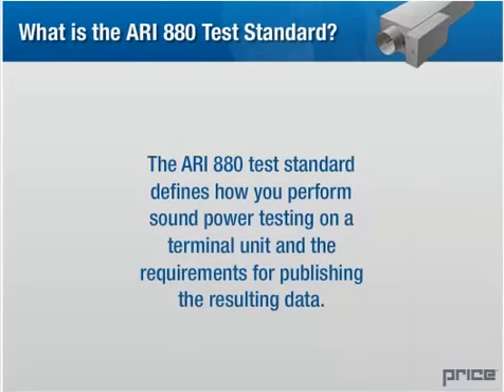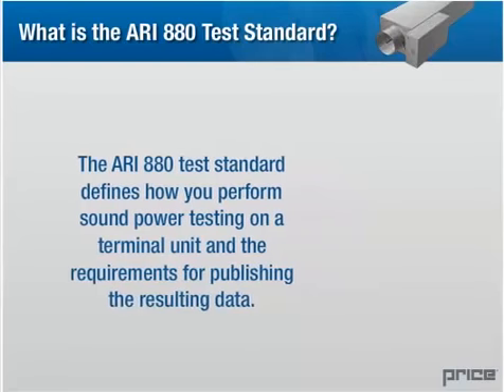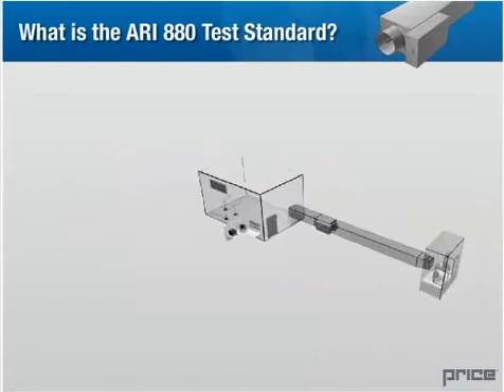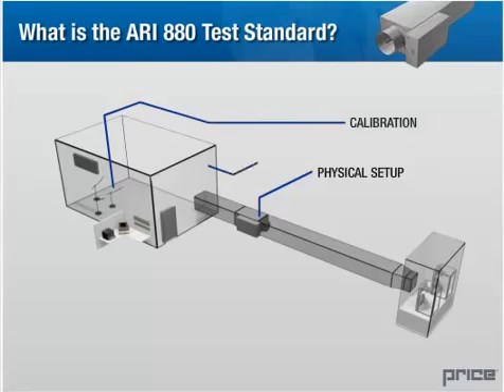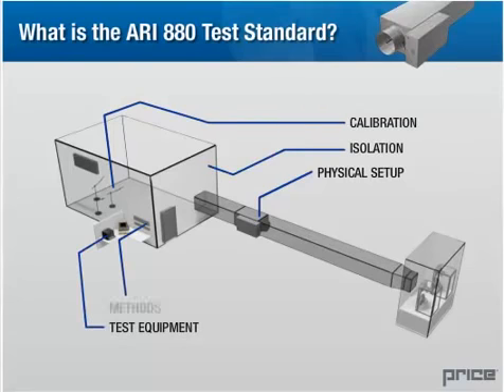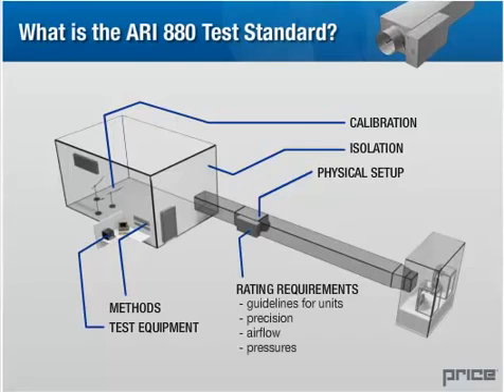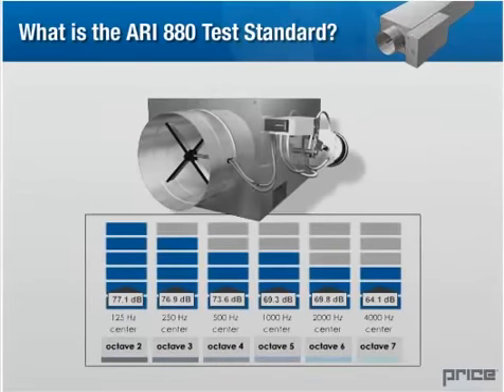The ARI 880 test standard defines how you perform sound power testing on a terminal unit and the requirements for publishing the resulting data. This includes guidelines for physical setup, calibration, isolation, test equipment and methods, as well as rating requirements for units, precision airflow, pressures, and terminal unit settings. Using the methods outlined in the ARI 880 test standard, we determine the sound power levels produced by the terminal unit in 6 different frequency ranges, or octave bands. This is the raw sound that is produced by the unit in the absence of any external influences.